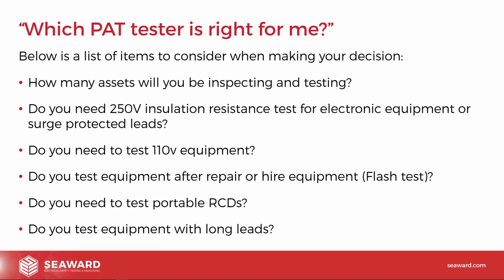Testing equipment with long leads. Obviously, all of our testers will test equipment with long leads, but if you've got something like a Prime Test 100, it may fail anything that's over 0.2 of an ohm because it sees the long lead as high resistance and it just says fail.